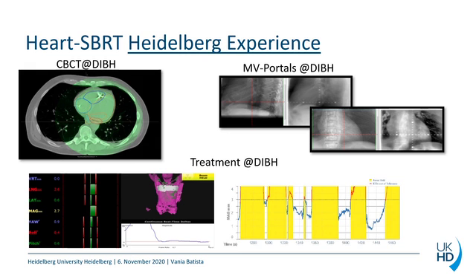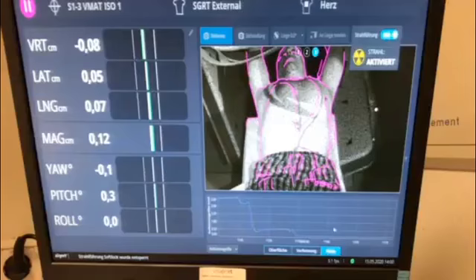The treatment is performed in deep inspiration breath hold with a tolerance of 3 mm and 3 degrees, and during the entire treatment there is an interface between the LINAC and Align RT, and if the patient goes out of tolerance, the LINAC stops.